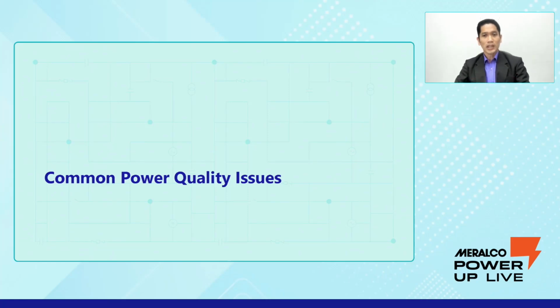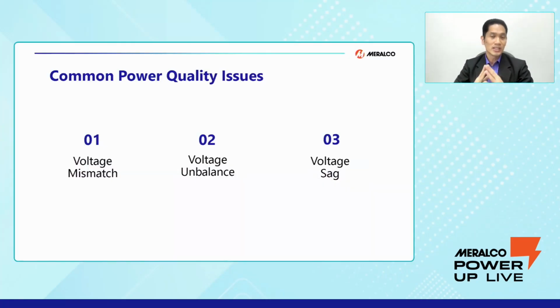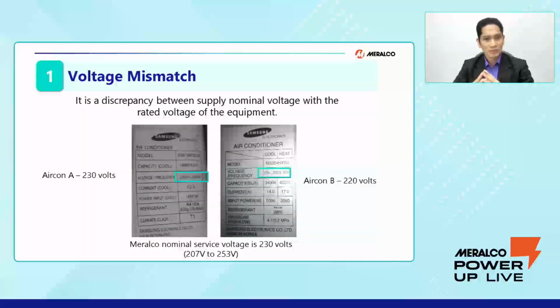So for the common power quality issues, first we have to discuss voltage mismatch, followed by voltage unbalance and voltage sag. Voltage mismatch is the discrepancy between the supply nominal voltage and the rated voltage of the equipment. In our example, we have an aircon A with a 230 volt rated voltage, and an aircon B with a 220 volt rated equipment voltage. They are the same manufacturer, but they have different voltage ratings.